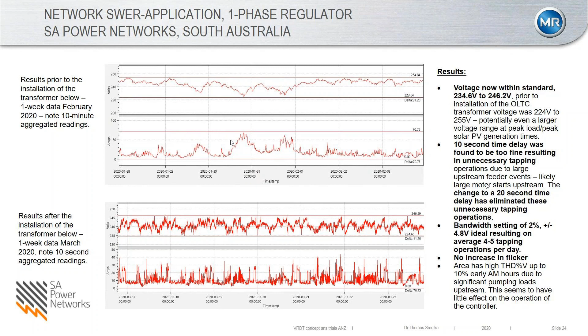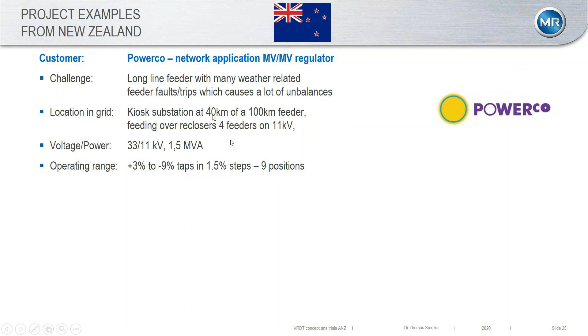Last but not least, there's another MV regulator installed in New Zealand with Powerco, really long feeders, so they have a lot of weather outages there. It's not really this reverse power flow from renewables thing in New Zealand; it's mainly to ensure that if they have weather impacts and voltage increases due to disconnection of some assets, they're still able to supply accurate voltage to all of their customers along this 40 kilometer feeder.